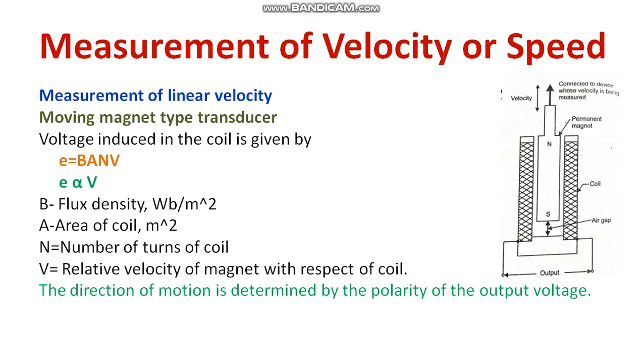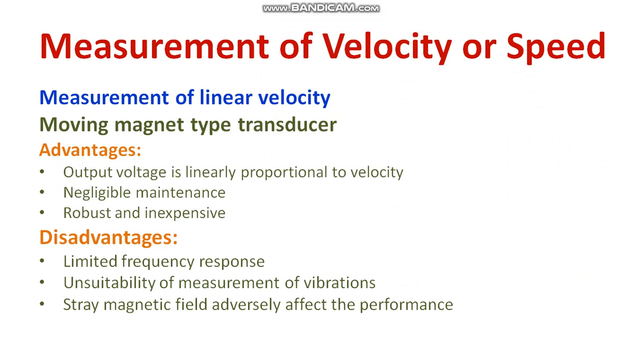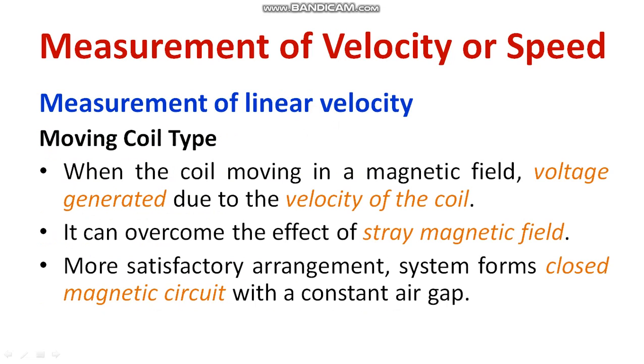Velocity is measured in terms of induced voltage. There are many advantages: maintenance is not necessary every time, construction is robust and quite inexpensive, and output voltage is linearly proportional to velocity, making measurement easy. If I talk about the setbacks: the frequency response is very limited, there is unsuitability for measurement of vibrations since slight movements cannot be measured, and stray magnetic fields adversely affect performance, introducing certain errors that require effective calibration.